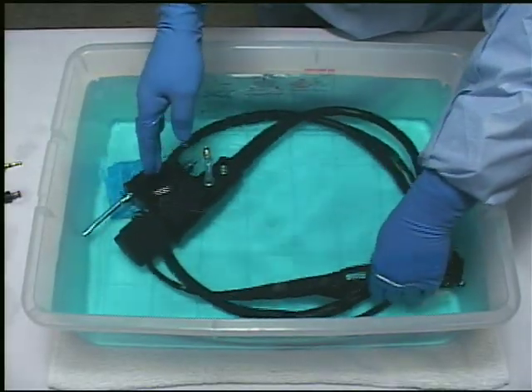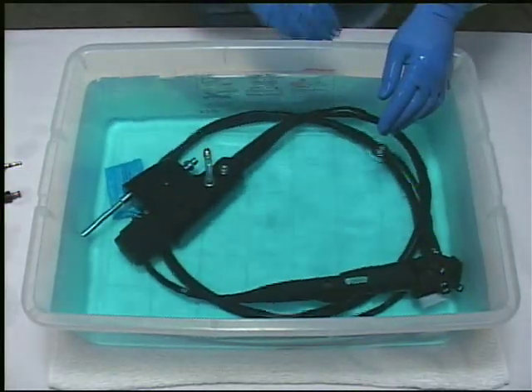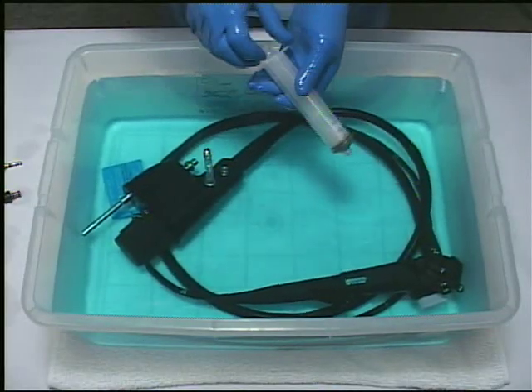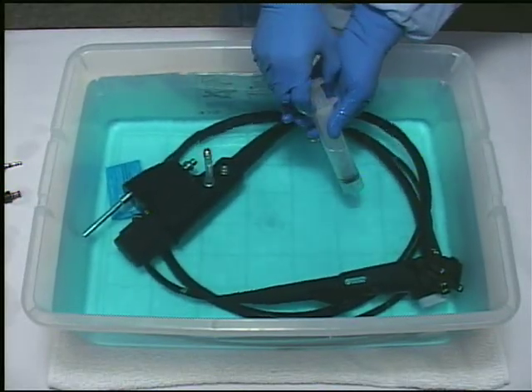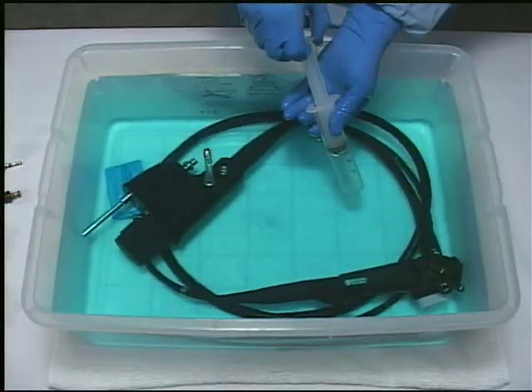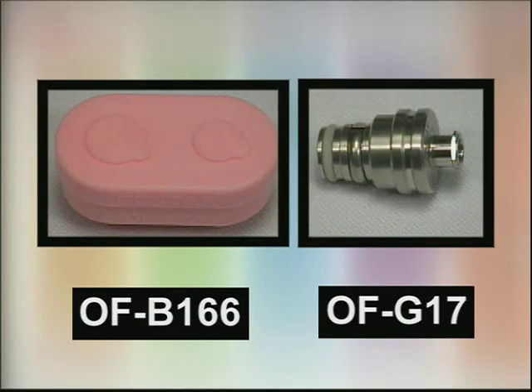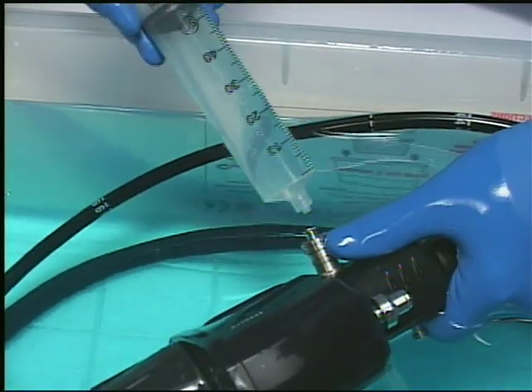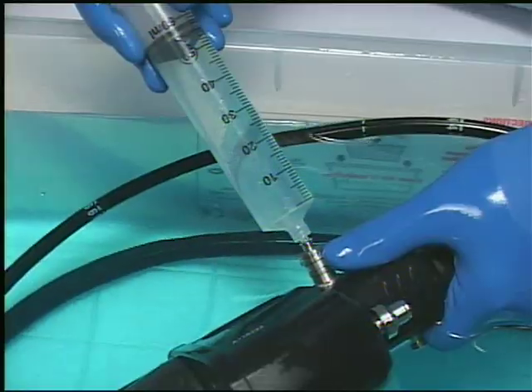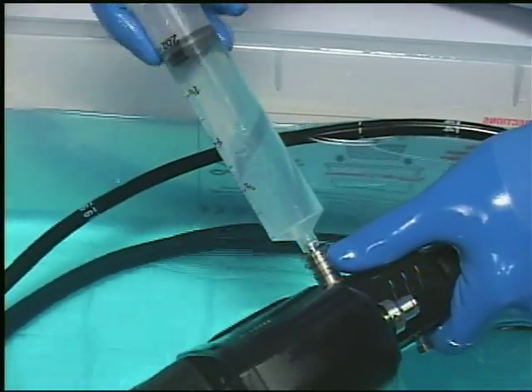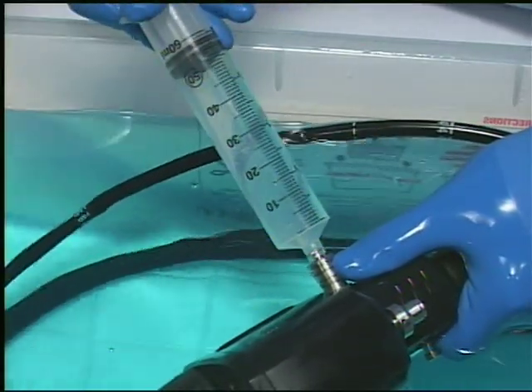Prior to high-level disinfection, the end user should confirm the minimum effective concentration, or MEC, of reused disinfectant as per the manufacturer's instructions. The air-water instrument channel disinfecting adapters, consisting of two separate components, OFB166 and OFG17, should already be installed on the endoscope from the previous cleaning procedure. Model OFG17 incorporates a standard luer lock connector to which a syringe should be attached.